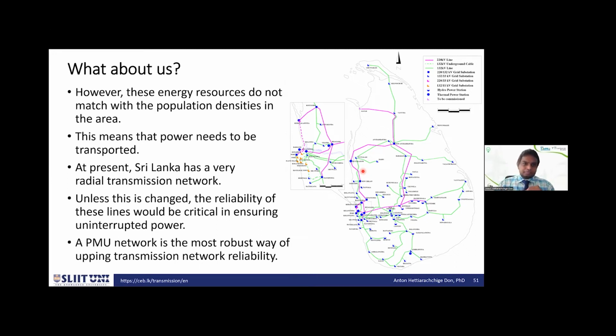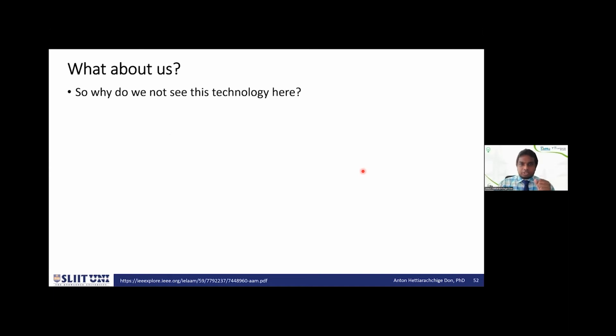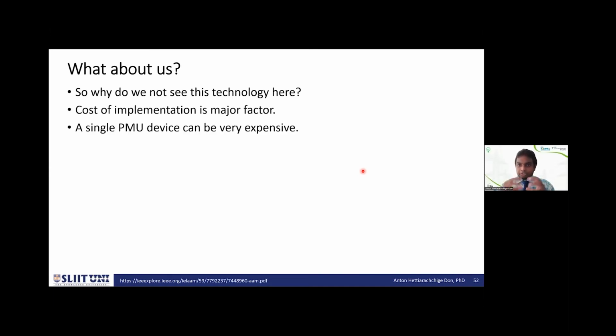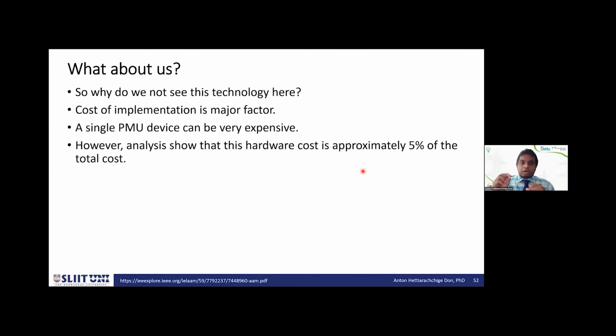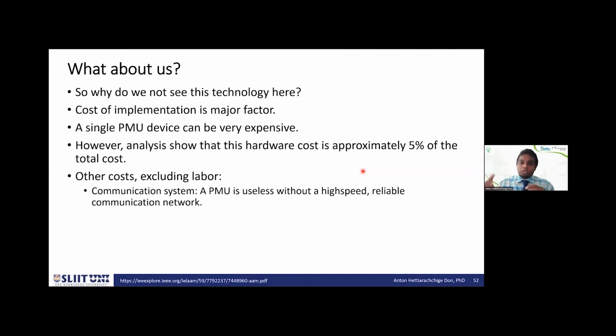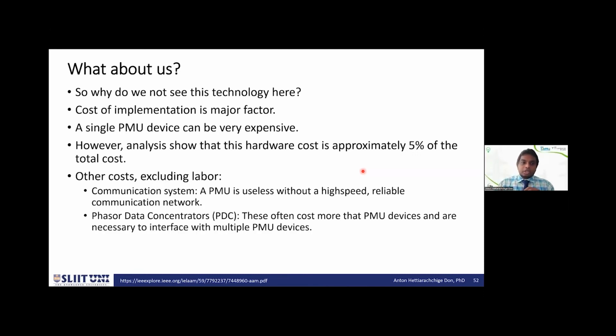But why is it not done? Mainly, it is a cost factor, right? A single PMU can be very expensive, just the device, but that's not the point. Analysis shows that the actual device is only about 5% of the cost. Why? Because it needs a lot of other things. So excluding labor, you need to think about a communication system. You need a high-speed, reliable communication system that connects to all these remote locations where PMUs are located. You need PDCs and other infrastructure for the network. You need security because now you are transmitting through the internet. You need cybersecurity infrastructure. So all these things add up, and the actual physical thing, although it's very expensive, is only about 5% of the cost, at least in the analysis done in the United States.